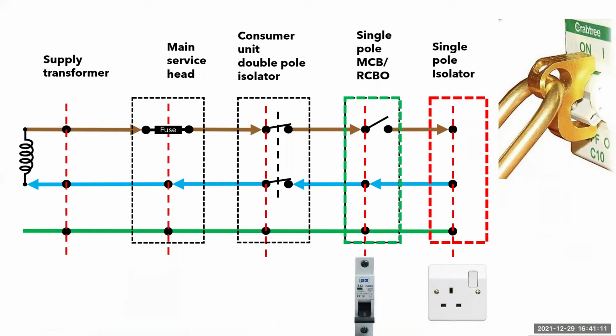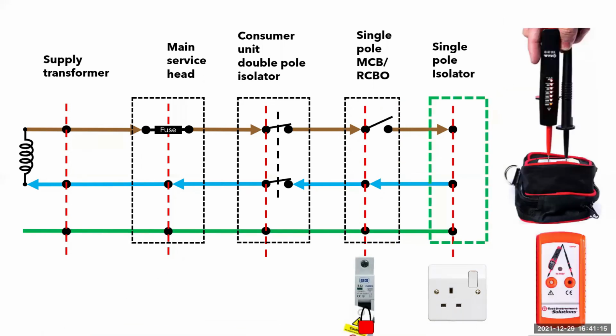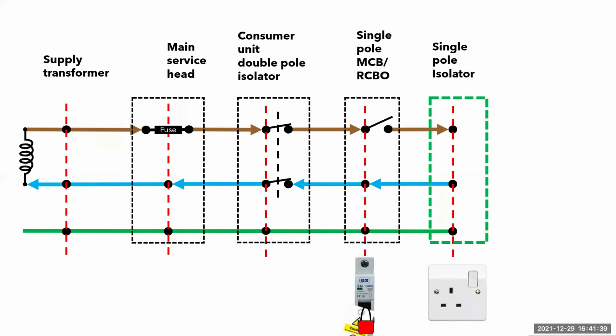All that's left to do is to prove that the socket has been de-energized, because there shouldn't be any supply to the socket terminals that LEDs won't light. So don't forget to prove that your voltage indicator is working correctly first. Otherwise, how would you know? Without this vital step, you will fail with safe isolation, as there is the slimmest chance that the power could still be on. The circuit is potentially de-energized and unable to be re-energized due to the lock-off on the MCB.